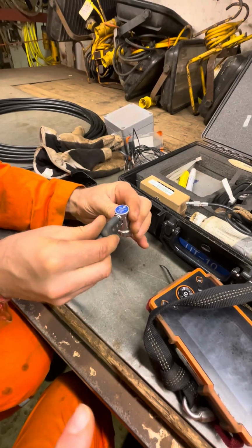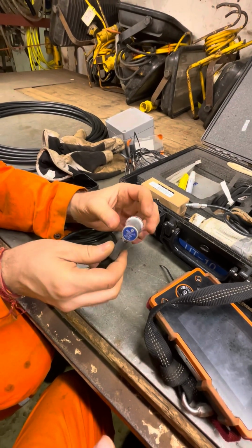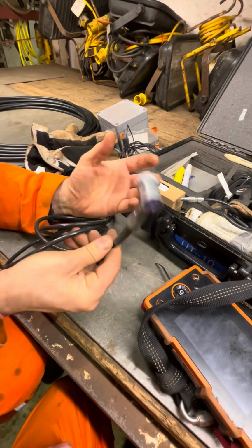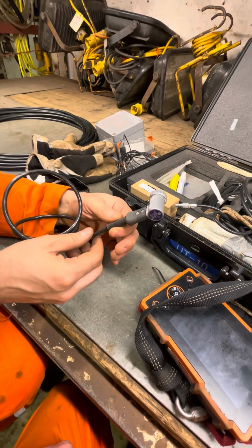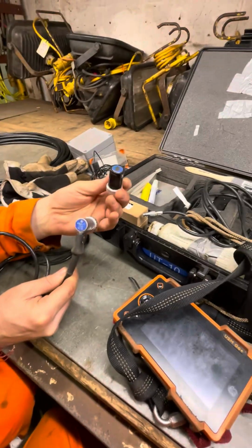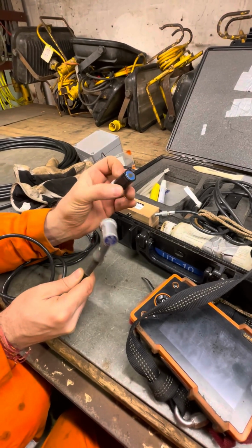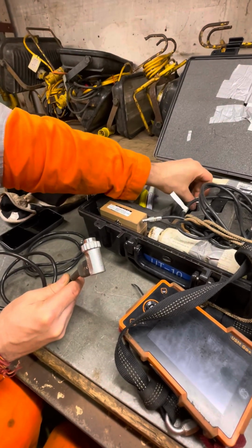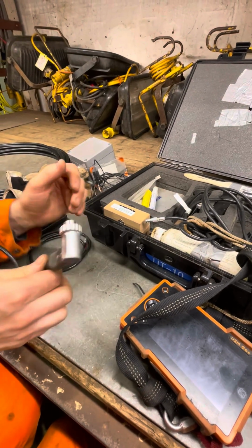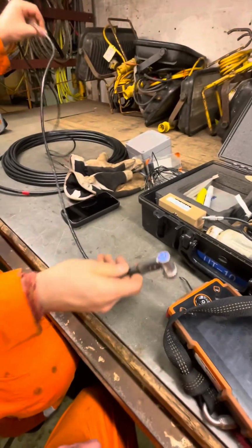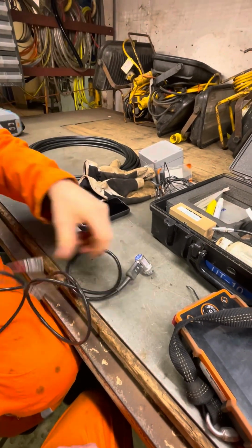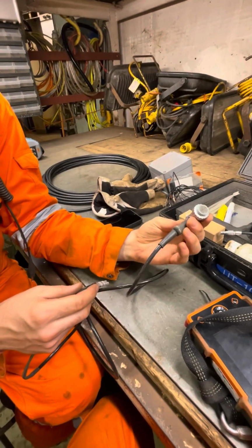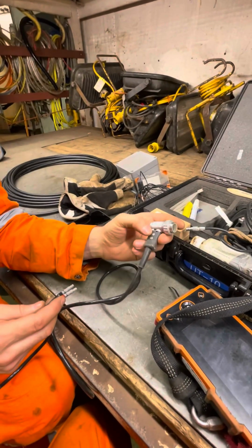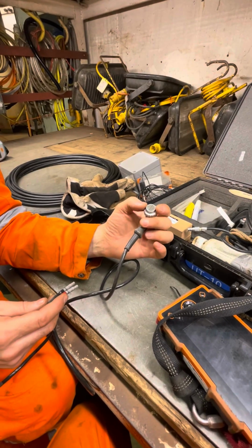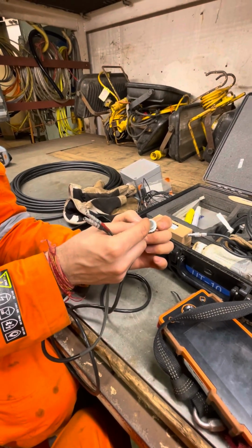So, does the client order this, or can we choose what we need ourselves? The probe. They send us. So, to measure thickness, this is a standard probe, but they're kind of universal, and I don't really like them. In some cases, they just don't do their job, but usually they only send us this, and we work with it. Sometimes there are specific pipes. For example, if the thickness is 3 millimeters or 4 millimeters, you need a different one. As for the probe, it's best to use either a 2-inch pipe or a 3-inch one. The diameter should already be set. If it's smaller, that's fine, we insert it.